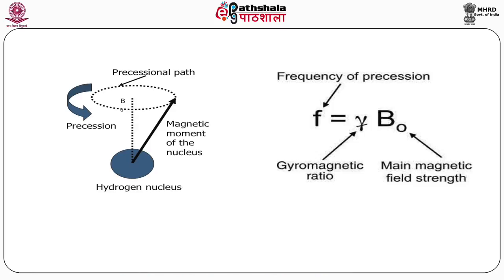For example, at one tesla magnetic field the Larmor frequency is 42.57 MHz, at 1.5 tesla it is 64 MHz, and at 3 tesla it is approximately 127.7 MHz. This frequency is unique for hydrogen nuclei. Other nuclei are also present in our body but their Larmor frequency is different. Hydrogen is unique in that it has high abundance and a high frequency of precession. Therefore, hydrogen nuclei are chosen to produce the MR signal in MRI. The hydrogen nuclei behave like magnets, more nuclei align along the main magnetic field creating a net magnetization, and these nuclei precess at 42.58 MHz at one tesla, though not in phase.